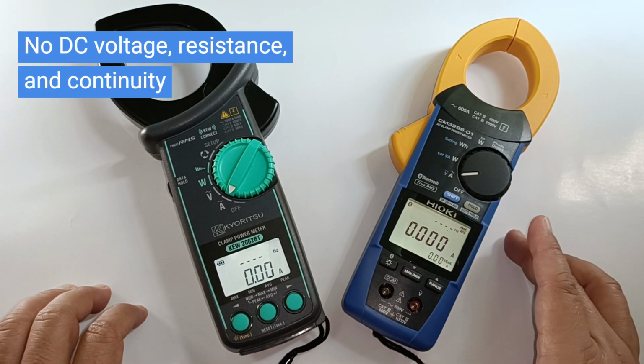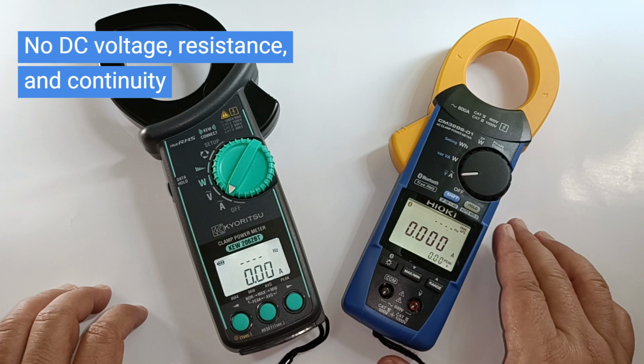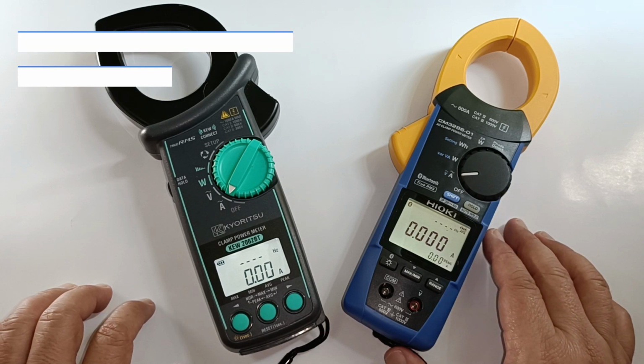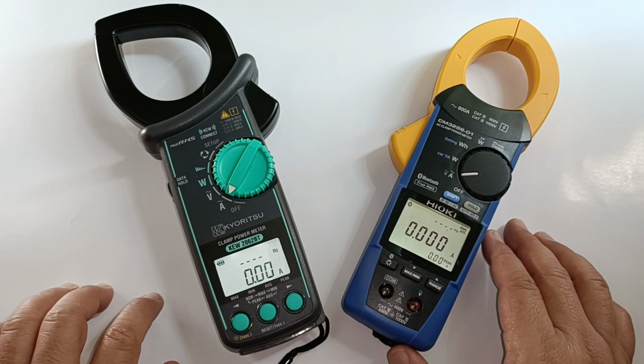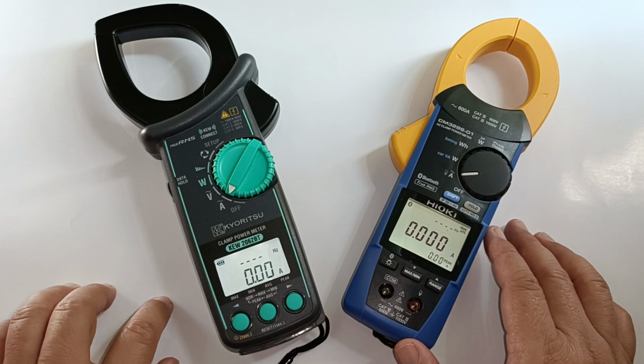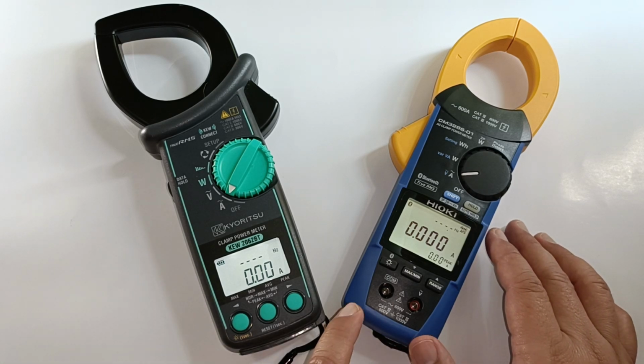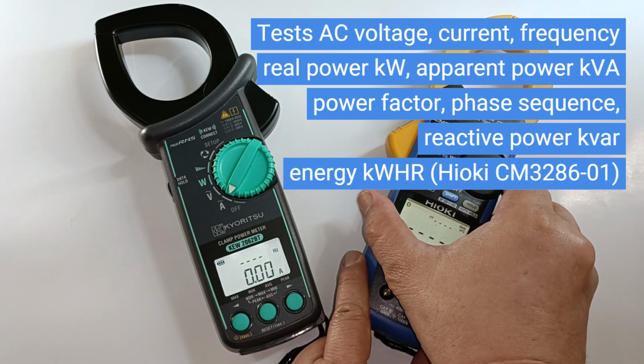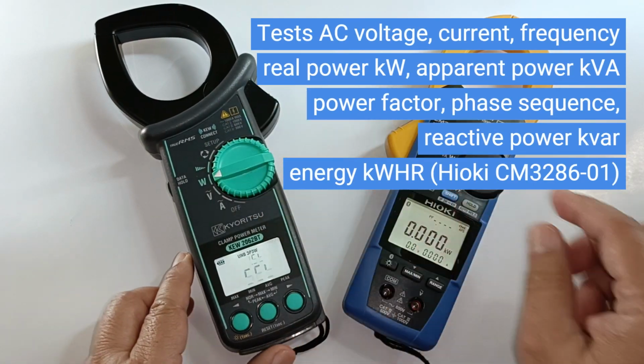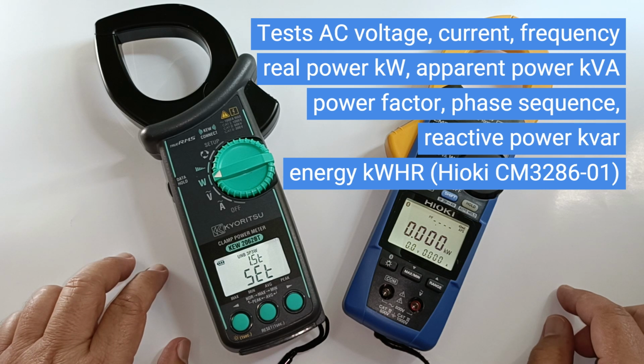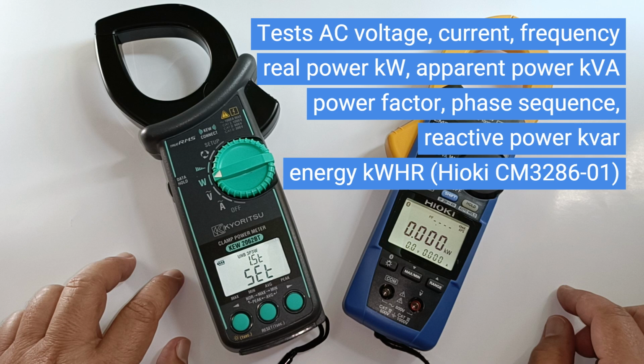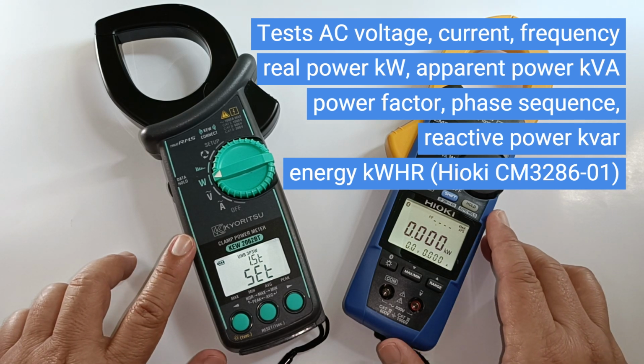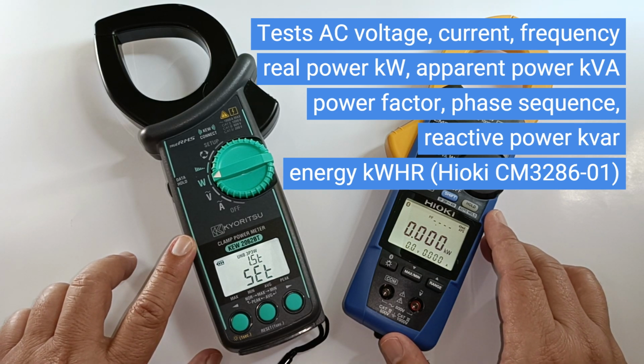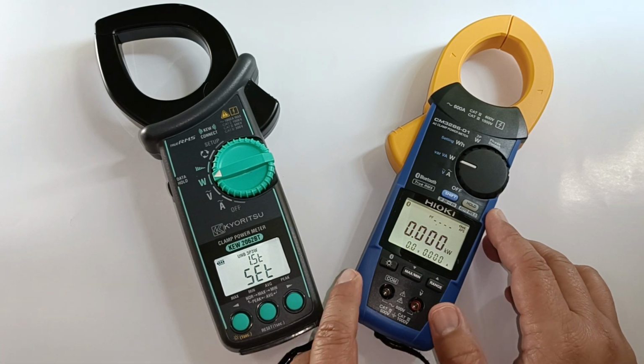You will notice that they don't have a DC voltage function, just AC voltage and AC current. Also, you won't find resistance and continuity. What you will find here is their ability to measure AC power, that is, real power in kilowatts, reactive power in kVAR, and power factor. They can provide this in either single-phase or three-phase, balanced or unbalanced. They can also detect phase sequence of a three-phase voltage source as well.